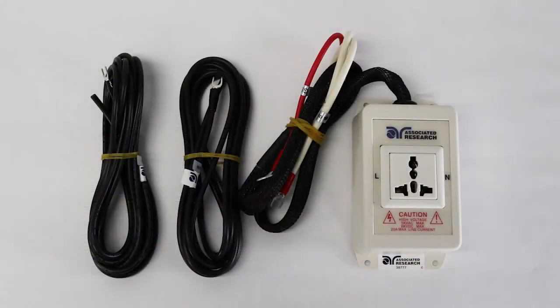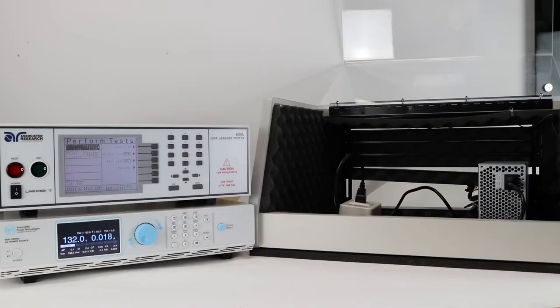In order to connect the LINECHEK to a power supply and the DUT, you will need the following accessories: a 2-probe line cord with a line conductor and a neutral conductor, terminated with lugs for an easy and secure connection to the DUT power input terminal of the LINECHEK. We will also be using an adapter box to connect the DUT. This instrument is rated to handle up to 40 amps of continuous current for the DUT. All input and output cables and adapter boxes used for testing must be rated appropriately.